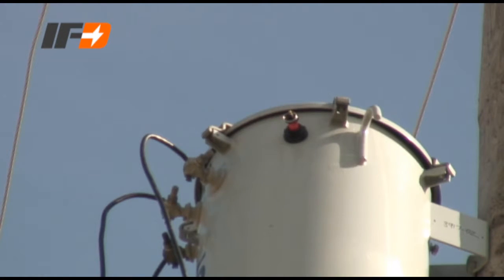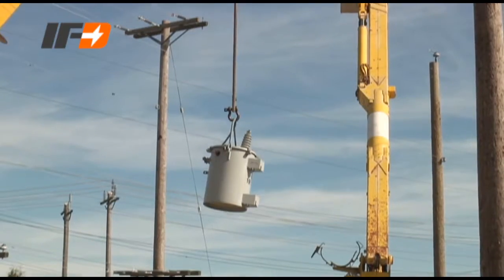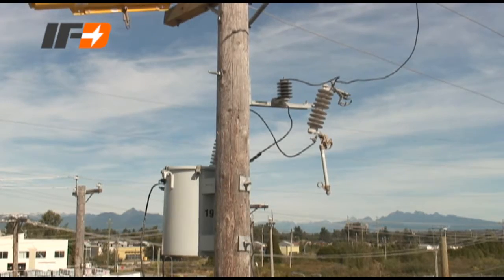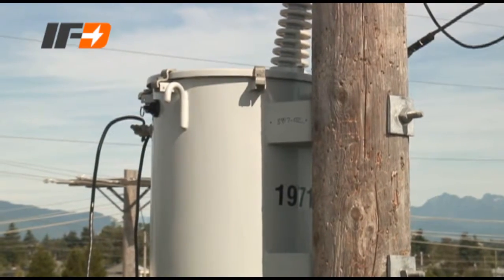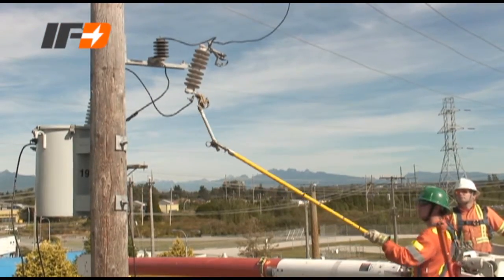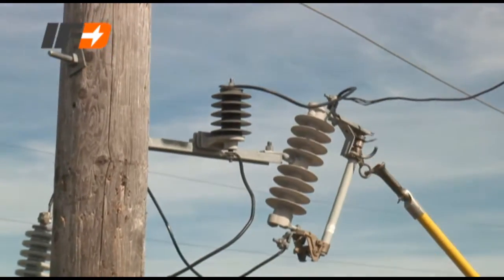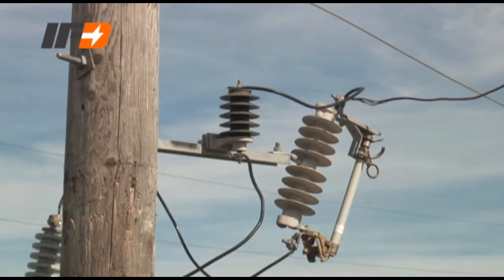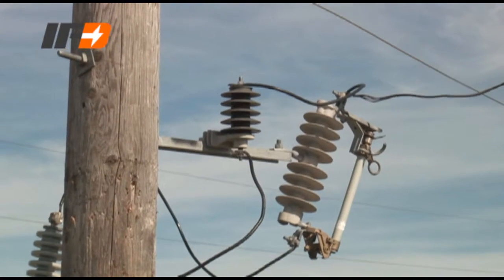An IFD-equipped transformer with a highly visible orange flag displayed must be taken out of service and replaced. If the fuse cutout is open but the IFD is not activated, the chances are the transformer is okay to be re-energized, providing all normal fault checks are done. Nothing can be considered 100% when it comes to safety.